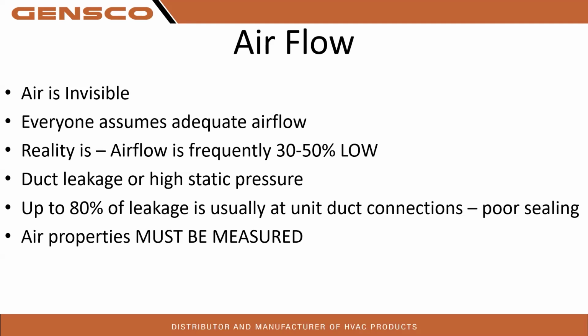we are typically undersized when we start going to add heat pumps and variable speed and whatnot. Flex duct is quite a bit less CFM rated for CFM. I'll show you the flex duct calculator at the end.